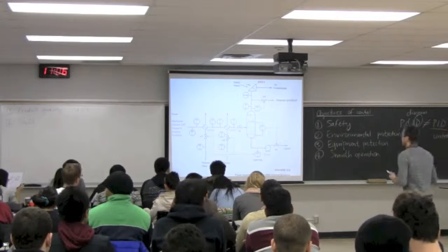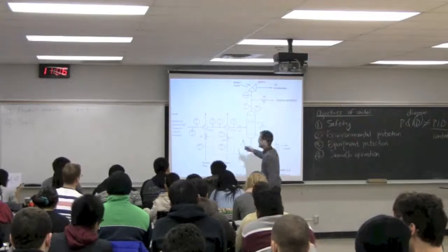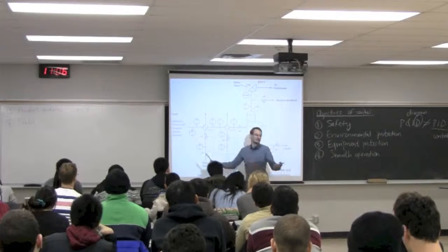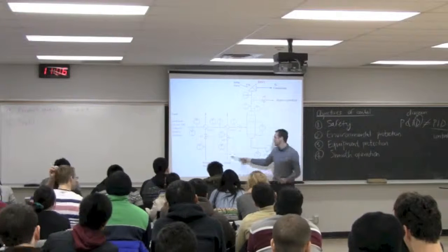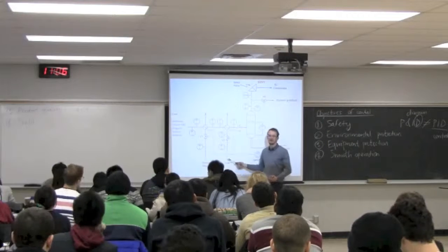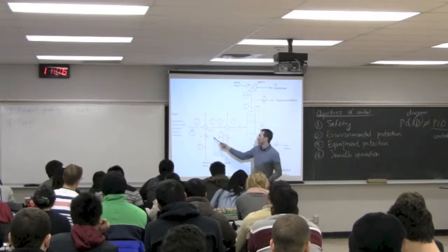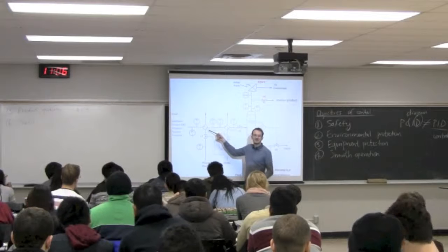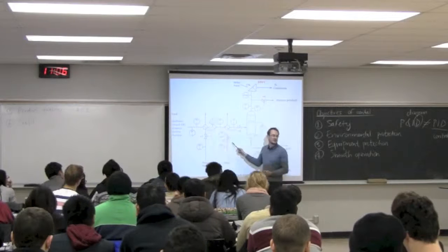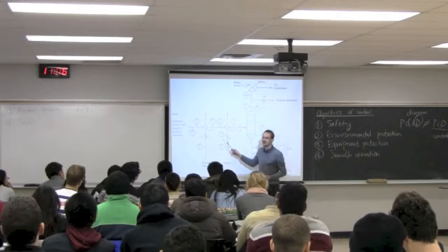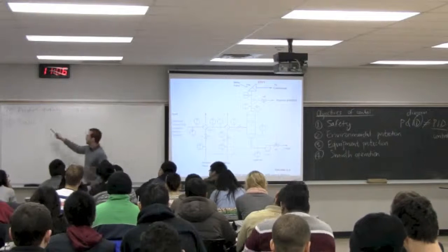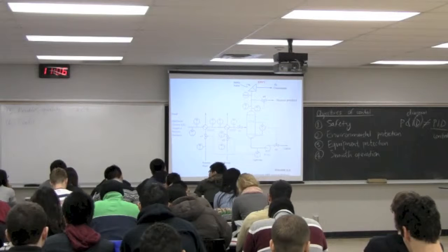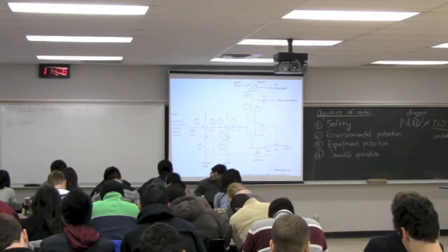Devin's saying it's cheaper to manipulate V1 than it is to manipulate V2. Right? This hot process fluid is there on our process anyway. Steam is something we have to create and put money into. We have to buy fuel to create steam. So what we'll do is open V1, and when V1 gets to 100% open, and let's say we still need more heat, then we'll start to switch over to V2. So that's profit. We design our control loop so we can maximize profit. Another way of saying that is we try to minimize cost. So first use your cheaper forms of heat and then switch over to your more expensive.